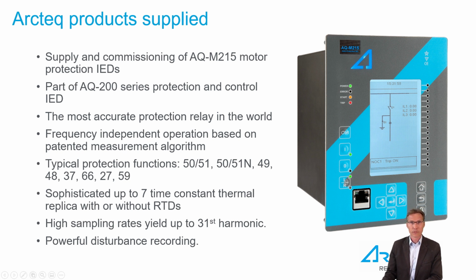Typical protection functions: motor overcurrents, jams, thermal overloads, startup protection supervisions, under and overvoltages, etc. Basic set of protection functions. AQ-M215 and all Arcteq motor relays provide a sophisticated thermal replica, with or without RTDs, with up to 7 time constants, or for simplicity, just a single time constant operation, user selectable.